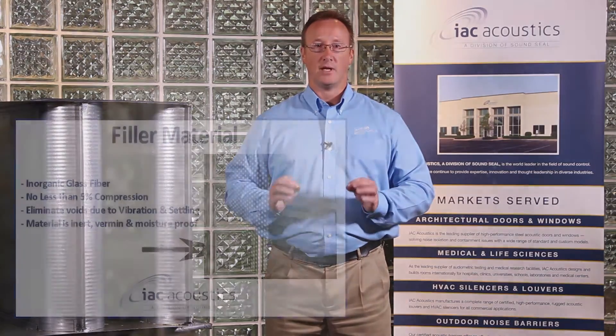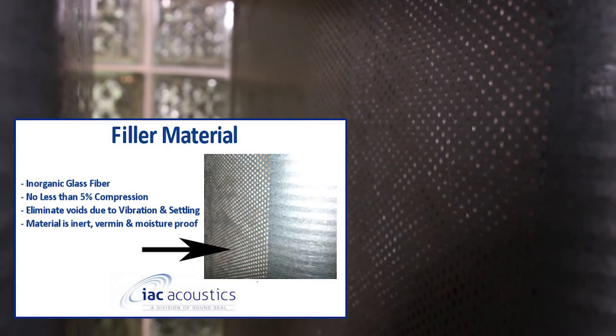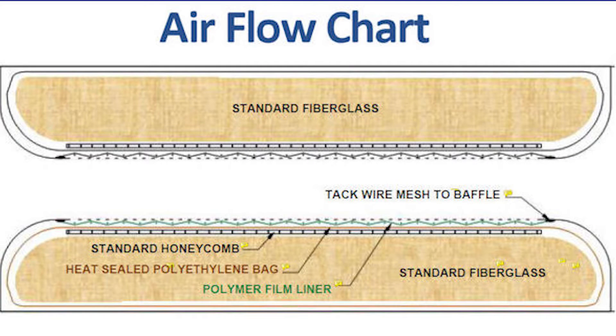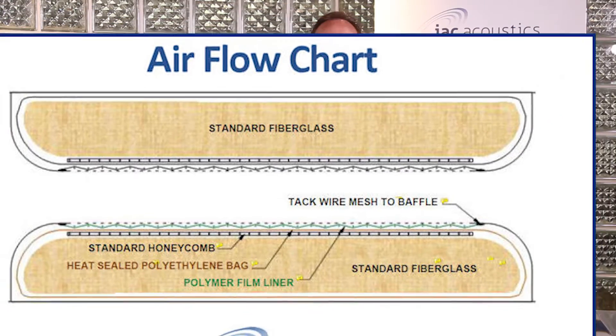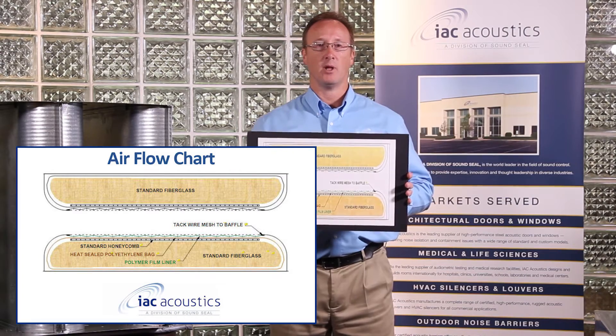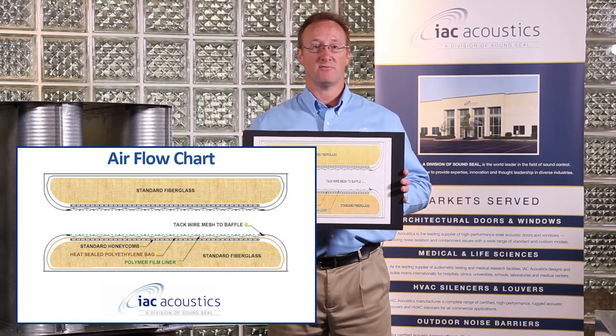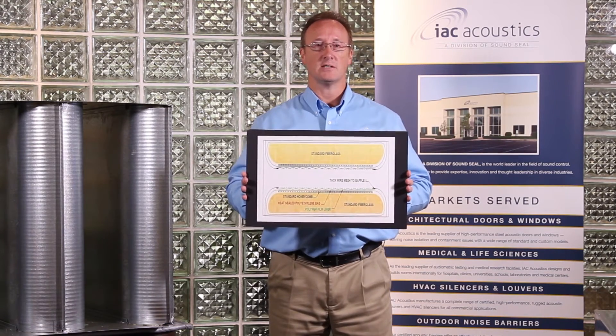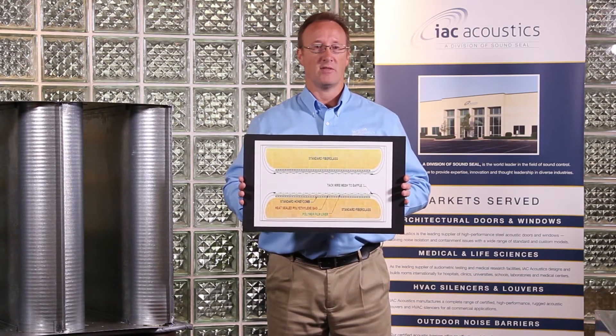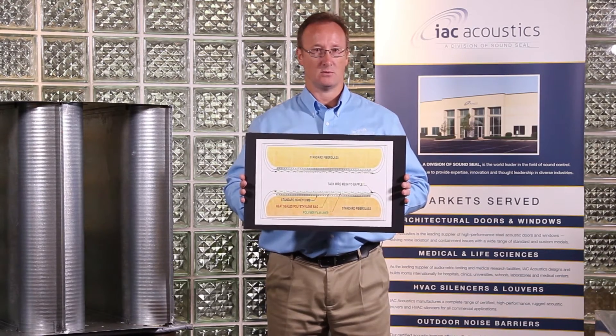Behind the perforated material is where the filler material is. It is inorganic fiberglass packed to no less than five percent compression, and is inert, vermin, and moisture proof. Here we see a typical inside geometry of the silencer. As an added option, you can apply a polymer film liner that encapsulates the acoustic media film for added protection. Better yet, IAC has the ability to provide heat sealed bags, which provides an even greater reassurance that fibrous material does not enter into the airstream.